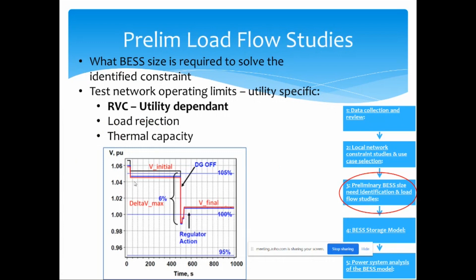I have here a graph that shows the concept of RVC. For example, you've got your initial voltage. When the storage was operating, say injecting power into the network, and it trips, the network experiences a voltage dip, and then your on-load tap changers from the transformers, voltage regulators, and other corrective equipment start to correct the voltage back to an acceptable level. The RVC is that dip that happens initially. You want to make sure that dip, if it does happen, stays within the allowed utility limits.